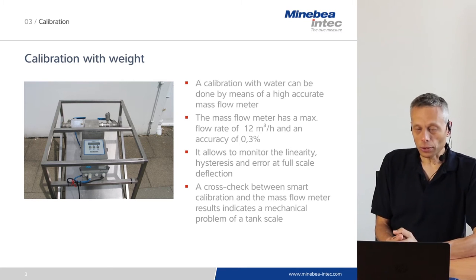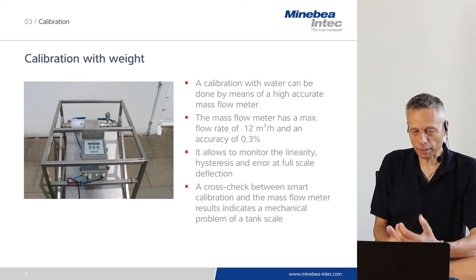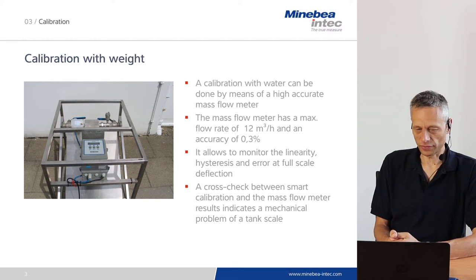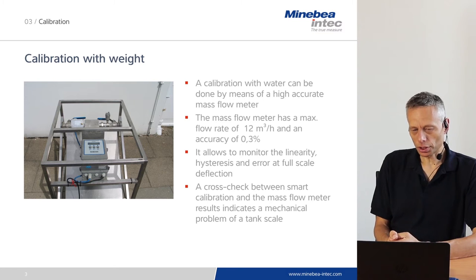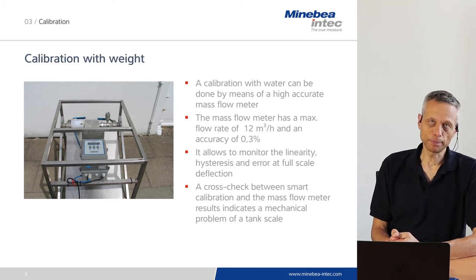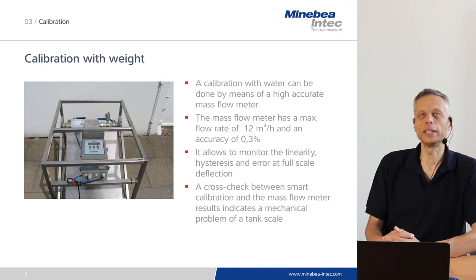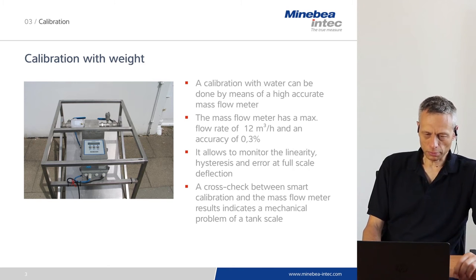Calibration by water allows you to monitor the linearity, hysteresis, and error at full scale deflection, step by step, of a process vessel scale. By using this flow meter and water, you can identify mechanical problems in a tank scale, because you compare the filling level and the readout of the mass flow meter with the readout of the weight display. So possible mechanical errors can be identified and corrected.